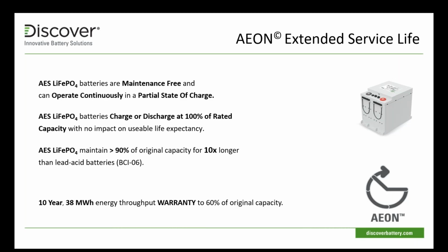The batteries are designed for a very extended period of service. Our design life is targeting some 20 years on that. And as you'll see in the statement below, our performance warranty covering 10 years on that. So these are maintenance-free batteries. One of their design features is that they operate continuously in a partial state of charge. They don't need to be at 100% of charge or discharged fully. You can do as needed, as pleased on that. That is a significant advantage in off-grid world where charging from sources is not always reliable on that. So partial state of charge is a very beneficial feature for off-grid, and we have it there.